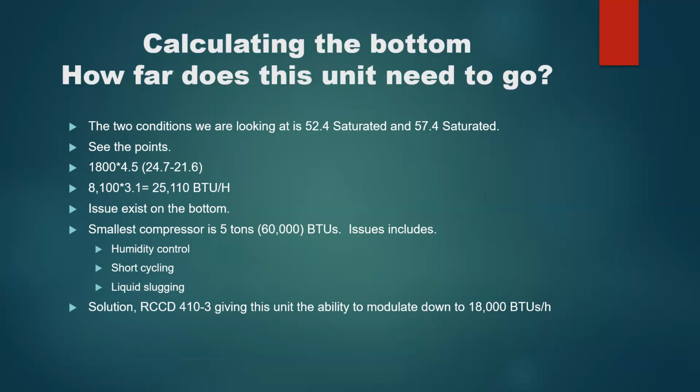The key is being in that sweet spot between dew point and freezing. With the RCCD, the key is to keep it as high as reasonably possible and still maintain the unit, because you'll extend the runtime, you'll get more dehumidification, everything will work better, and that coil will become saturated according to what the TXV is set for superheat.